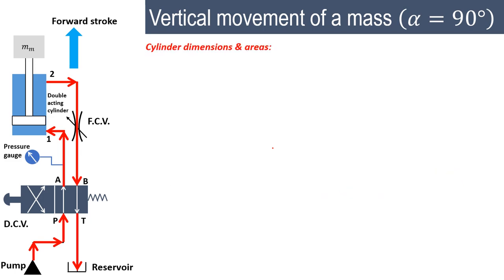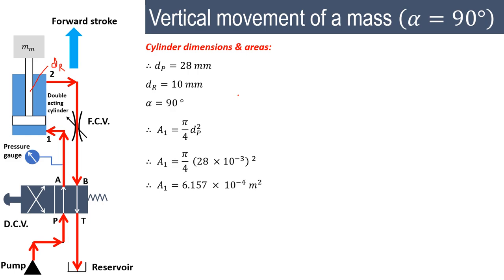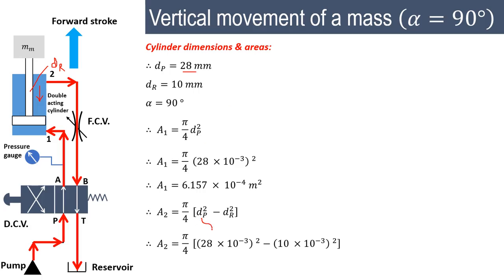With dp = 28 mm and piston rod diameter dr = 10 mm, and alpha = 90°, we calculate the areas. The piston area A1 = (π/4)·(28×10⁻³)² = 6.157×10⁻⁴ m². The effective piston area during the return stroke, A2, is obtained by subtracting the rod area: A2 = (π/4)·(dp² − dr²) = (π/4)·[(28×10⁻³)² − (10×10⁻³)²] = 5.372×10⁻⁴ m².